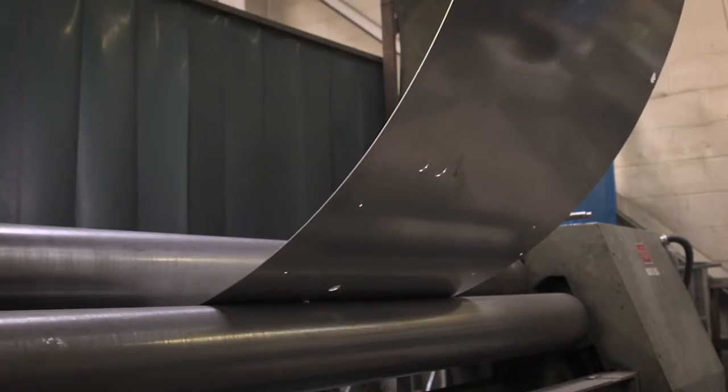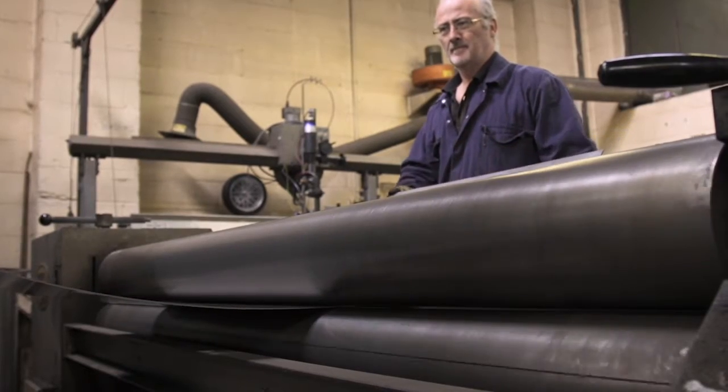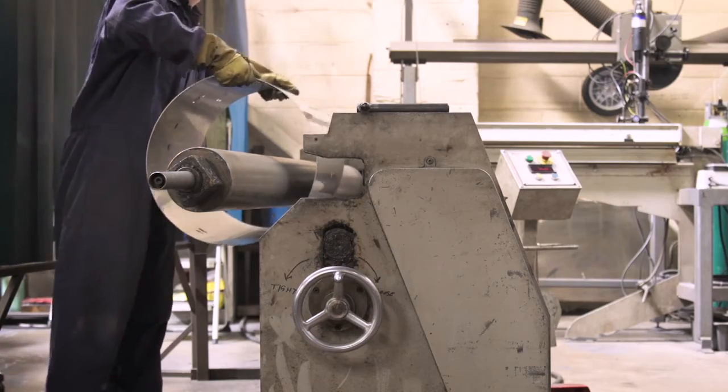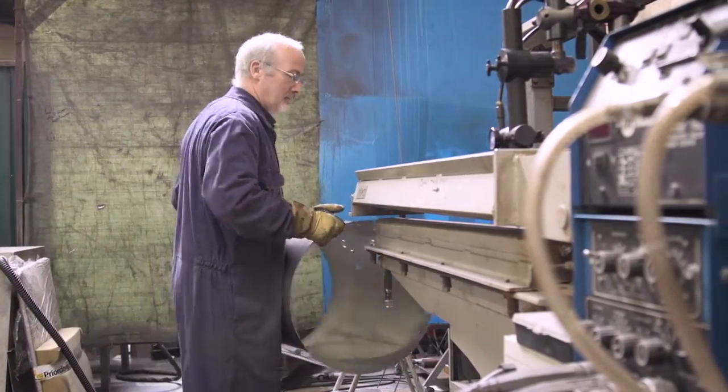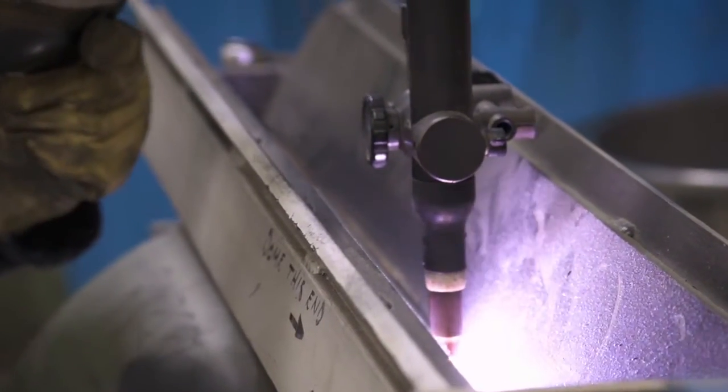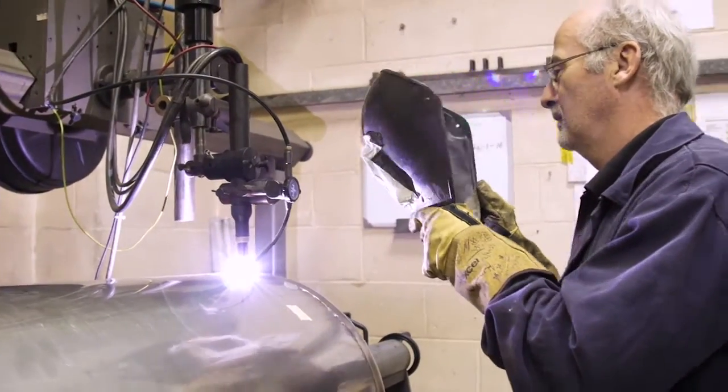The pressure vessel wall is formed from a cut and punched flat panel on a rolling machine, making a gentle roll to bring two outer edges together. An automatic seam welder is then used to produce a straight and smooth seam weld. Next, a large end cap is welded to the tube to finish the basic chamber construction.